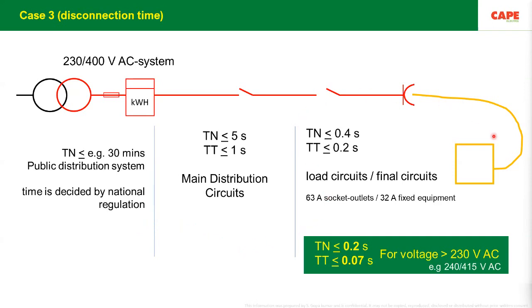For a fault, you can see here what I have shown: this is a transformer. You have a meter, meaning your point of commencement of supply, your main distribution, where I am moving the cursor. Then you have your final distribution board. For final distribution boards, up to 63 amps socket outlets or up to 32 amps fixed electrical installation, the maximum allowed disconnection time is what is shown here: 0.4 seconds in case of a TN system, 0.2 seconds in case of a TT system. At the same time, for the fixed electrical installation, the main distribution boards, the disconnection time is the tripping time of your MCB, which can go up to 5 seconds in case of a TN system and up to 1 second in case of a TT system.